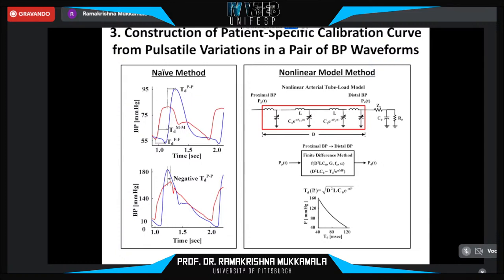In this way, PTT for each and every blood pressure level in the cardiac cycle is effectively estimated after mathematically eliminating the reflected wave, and the resulting BP-to-PTT function can be used as a patient-specific calibration curve. So by measuring a proximal blood pressure waveform and a distal blood pressure waveform, we can arrive at a curve that relates PTT to blood pressure without invoking an intervention to change blood pressure, using this nonlinear model method.